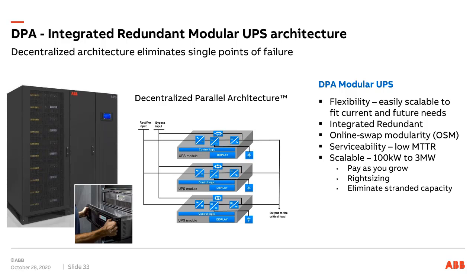The main benefit, actually, I guess there are two. One is that ABB Modular UPSs offer integrated redundancy due to the decentralized design. The other, which not all vendors or manufacturers of modular UPS offer, is what we refer to as online swap, which is essentially hot swap. You can swap a module on a running UPS. You can add a module, excuse me, on the fly on a running UPS. That doesn't mean customers are going to do that. Some customers may be more comfortable going to bypass, then adding or swapping the module, and then going back on the UPS. That can be done in a couple of minutes, but it can actually be done on the fly. The UPS is designed so that it can.